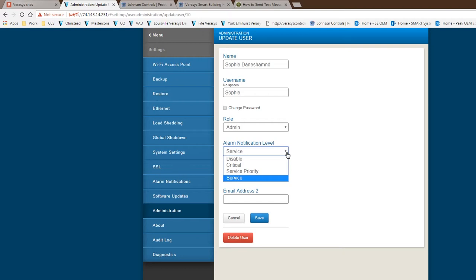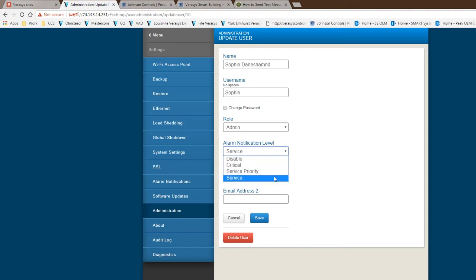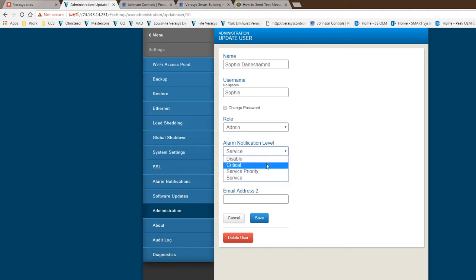The other thing, really recommendation more than anything, if you are setting up a user from a tenant perspective, you know, facility manager or whoever that's really around the system day to day, you really want to set them up as critical unless you really want to be notified on everything. Service, that's a lot of faults that can be generated and a lot of these are not important, more maintenance type alarms. If you are setting up for service, that's really for somebody that's maintaining this system.